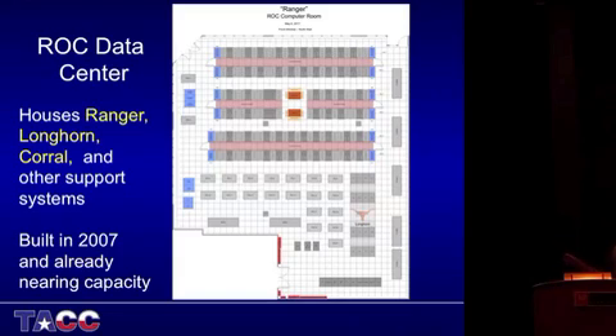Ranger occupies this space here. We use in-row cooling on it. All the other systems are actually cooled through the CRAC units on the side here, but they don't have quite the power density that Ranger has. Ranger is 30 kilowatts per rack, whereas most of the other racks in the room are somewhere between 15 and 20 kilowatts per rack.